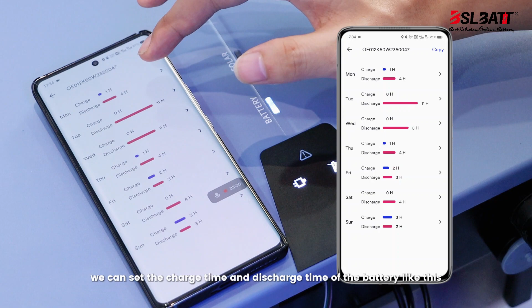In custom mode, we can set the charge time and discharge time of the battery. For example, on Tuesday, we charge for 0 hours and discharge for 11 hours. We can set the discharge time between 11 and 15 o'clock, and we can add a new time slot as we wish.